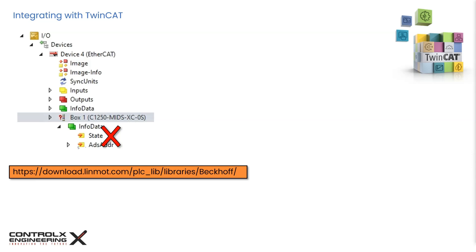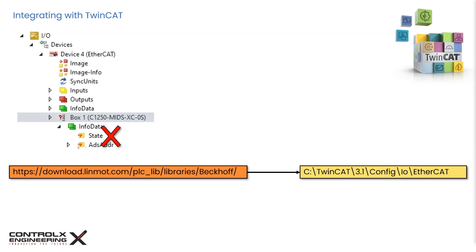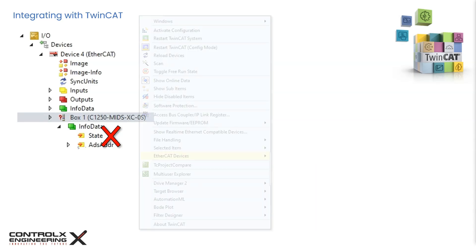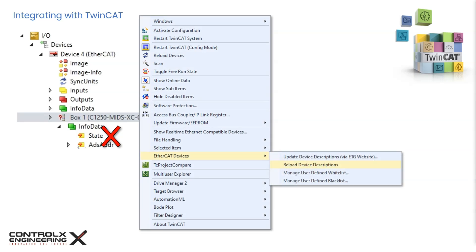For LinMot, the ESI file can be downloaded from this link on their website and the ESI XML file must be manually copied to this location in your TwinCAT XAE installation folder. When TwinCAT XAE is first started, it loads all the device ESI files from this location on startup. If the XAE is already open and the ESI file is then copied in the TwinCAT folder, then the device descriptions have to be manually reloaded by clicking on the TwinCAT menu item and selecting EtherCAT devices then reload device descriptions.